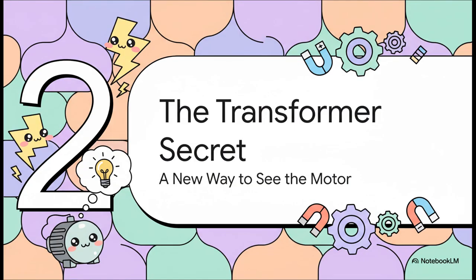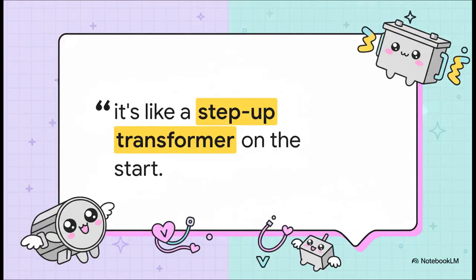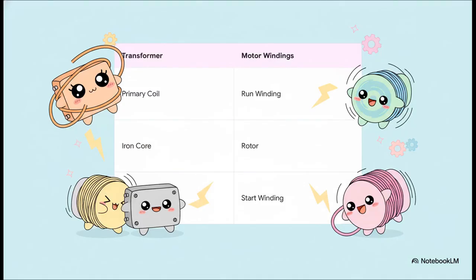So we've met our team, but how do they all work together to create that extra voltage? Well, the secret is you have to stop thinking about this as just a motor. This quote from our source material really nails it. For just a split second during startup, the parts of the motor stop acting like a motor and start acting like a step-up transformer. And here's how that analogy works. It's a pretty cool one-to-one comparison. The run winding acts like the transformer's primary coil. The spinning rotor in the middle, that's our iron core. And here's the kicker. The start winding, with all its extra turns of fine wire, acts as the secondary coil. And if you know anything about transformers, you know that's the key to stepping up voltage.